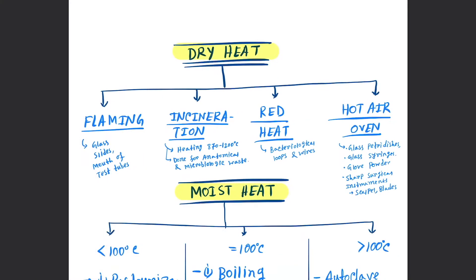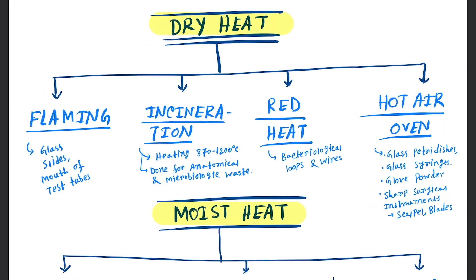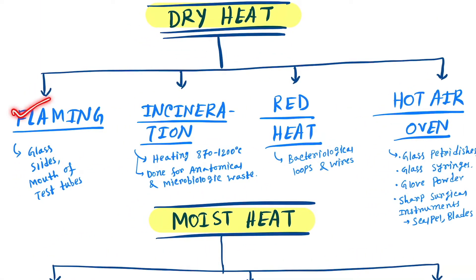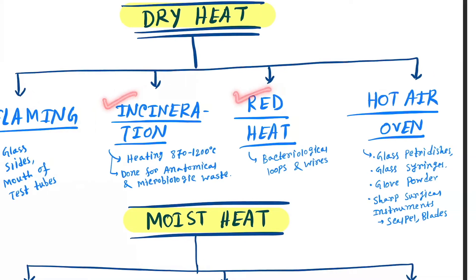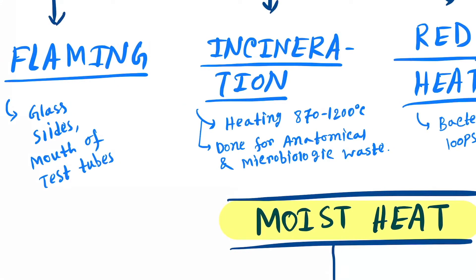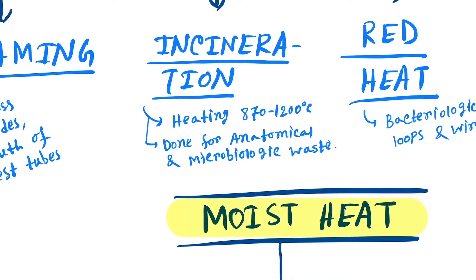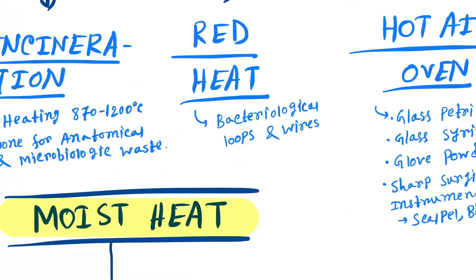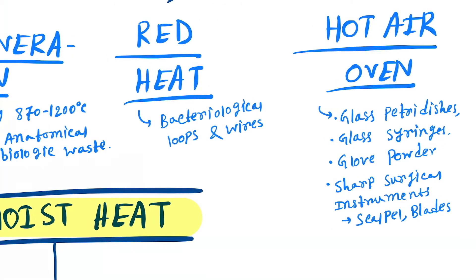Dry heat is of four types. First is flaming - we use flaming for glass slides and mouths of test tubes. Next is incineration: heating at 870 to 1200 degrees Celsius, done for anatomical and microbiological waste. Next is red heat for bacteriological loops and wires. Then hot air oven: we use it to sterilize glass petri dishes, glass syringes, glove powder, and surgical instruments like scalpels and blades.